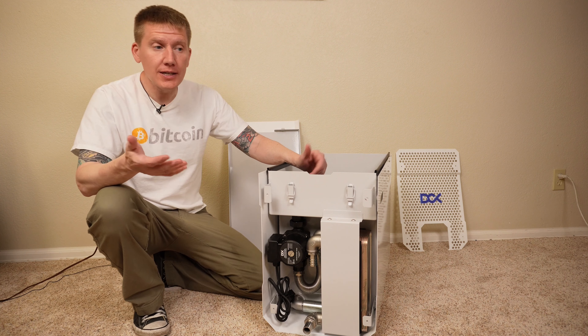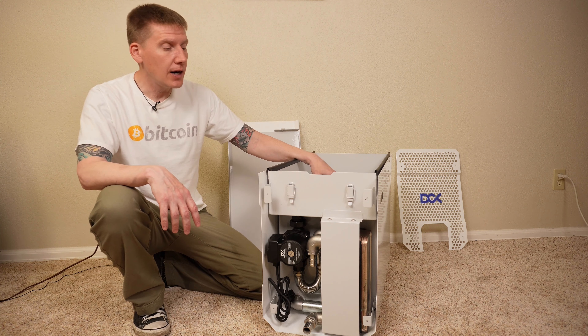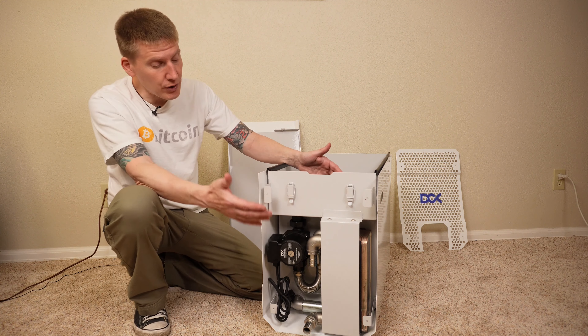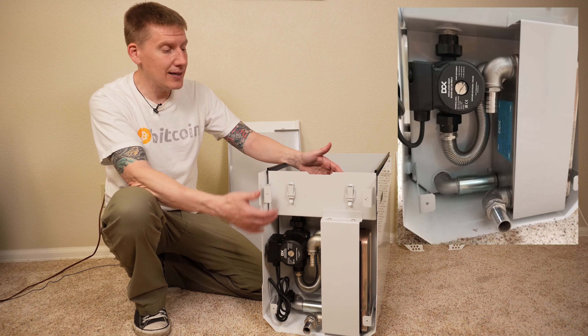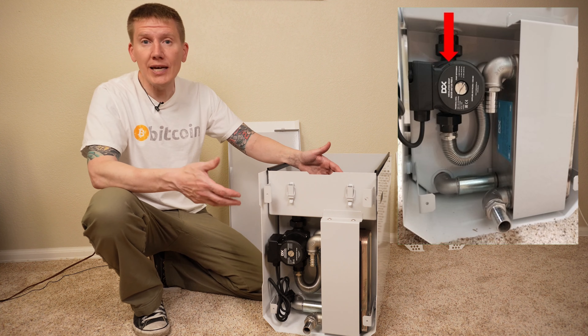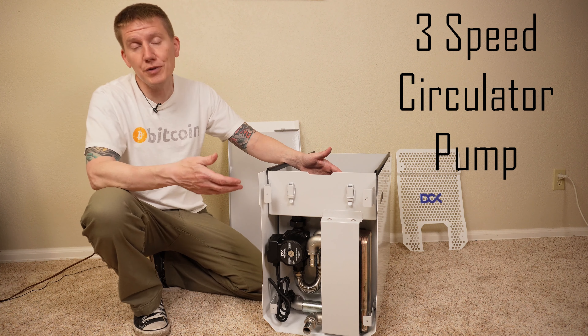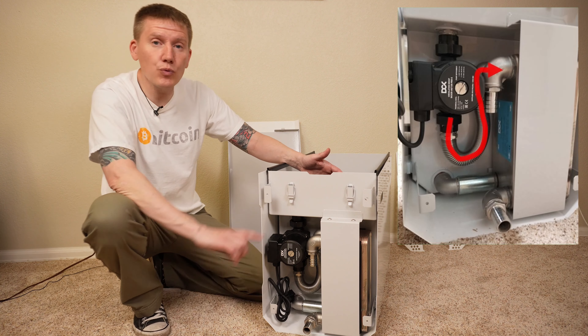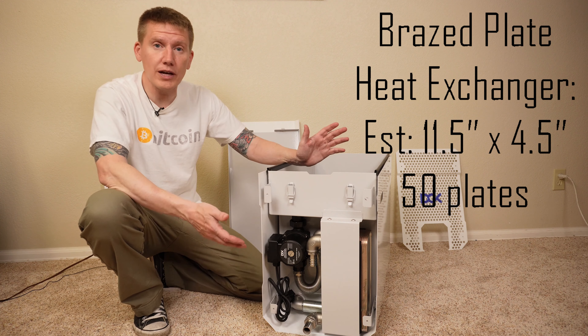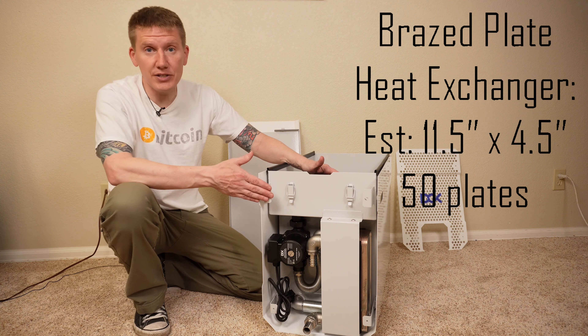As far as how this tank works, it works like any other immersion system. You have the main tank where the miners and bulk of the fluid go. After that you have the hot coolant recovery section. Below the hot coolant recovery is the pump. I really like the way they designed this — the hot coolant recovery drops right into the pump, so the pump is always going to be fully supplied with fluid and never be starved. The pump is a three-speed pump, giving you some variability in fluid circulation. The outlet of the pump goes directly into the heat exchanger, which is roughly four-and-a-half inches by a little over eleven inches with about 50 plates.